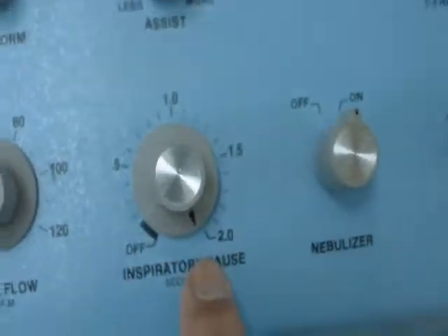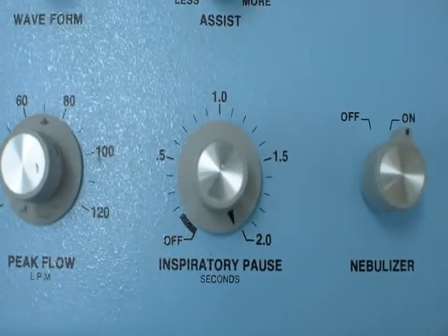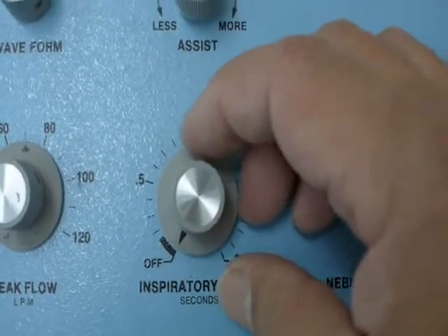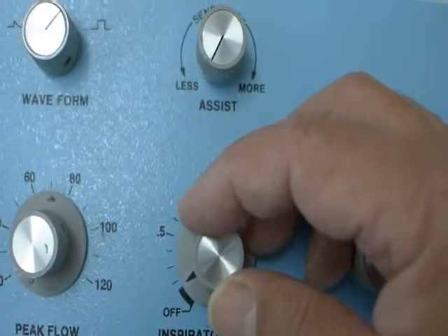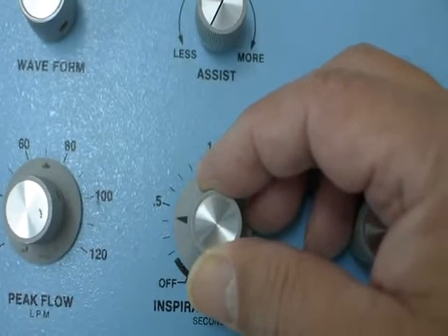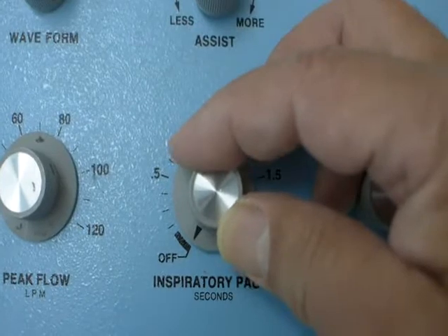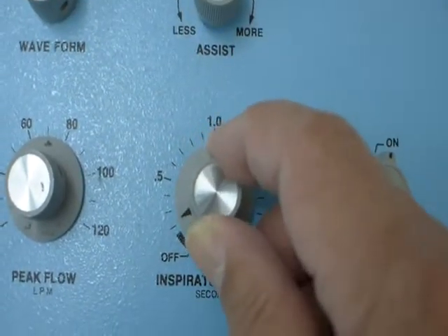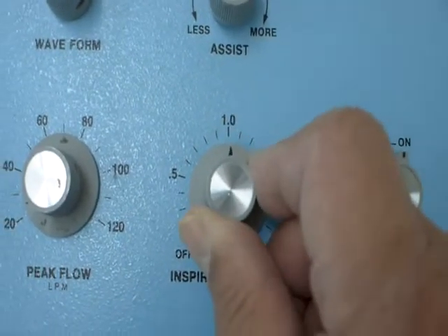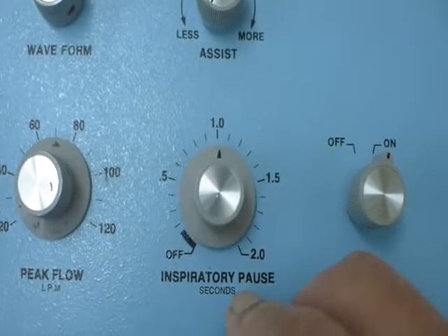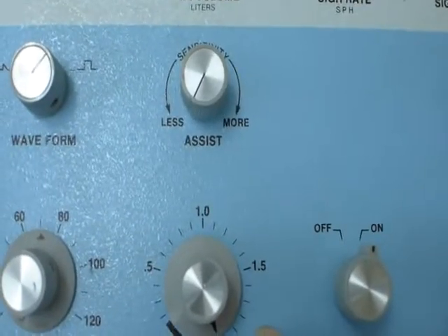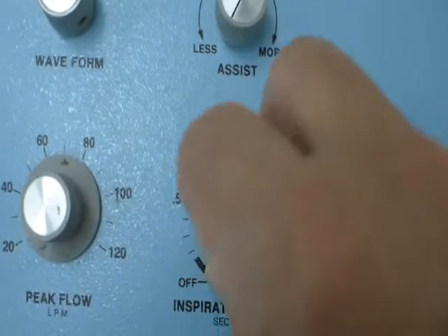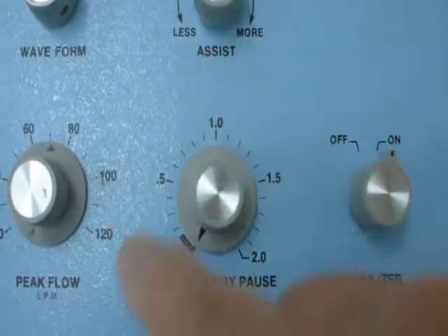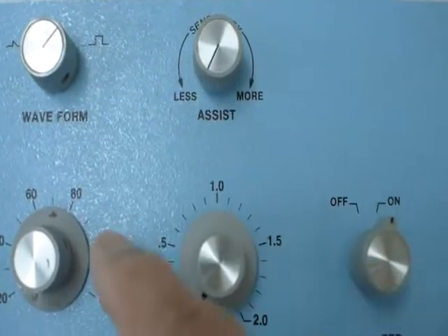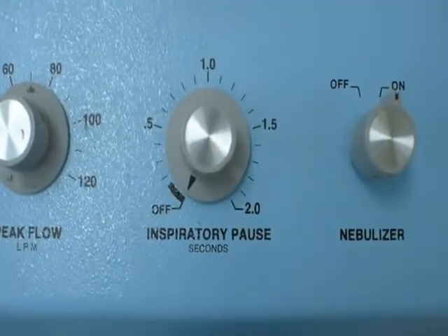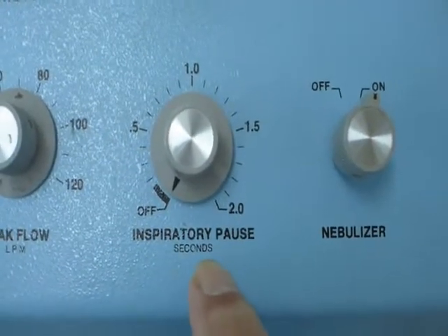Okay, and then the next one here we call the inspiratory pause. The inspiratory pause is the time when you breathe in and then hold your breath for a few seconds, and then you exhale. So here we are setting the machine to push the air into the lung of the patient and then hold it for 1 second, or 2 seconds, before it exhales. So you inhale, hold it for 1 second, 2 seconds, and then exhale. That's the inspiratory pause.